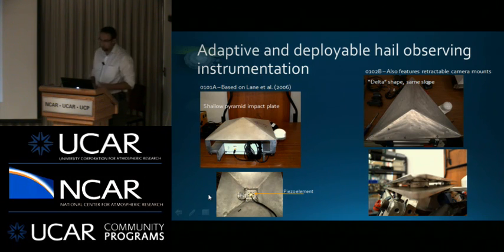We also notice if you try to use adhesive, you will definitely cause a voltage signal that can bias your information if you put adhesive on the piezo. So we use set screws, very, very tiny set screws that are off the ceramic portion of the disc, and they're all uniformly torqued to hold that piezo, so we don't bend it and induce a voltage bias. The same applies to the delta shape after we decided to go away from a piezo on each face.